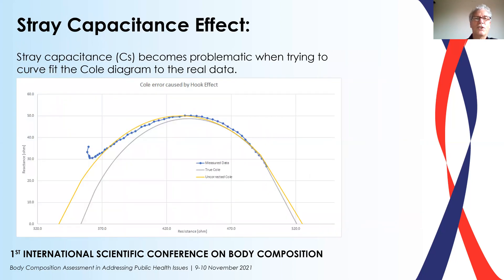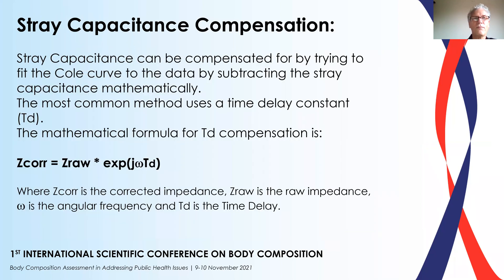In this diagram, we can show you exactly the problem. The blue dotted line is the actual physical measurement of the reactance against resistance at different frequencies. The grey line is a true Cole diagram, but if you look at the curve-fitted line — the yellow line — you can see that the R-infinity and R0 values would be quite different from what would be a true measurement. Stray capacitances can be compensated for by trying to fit the Cole curve to the data by subtracting the stray capacitance mathematically.